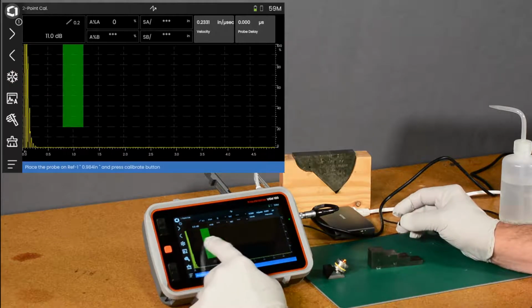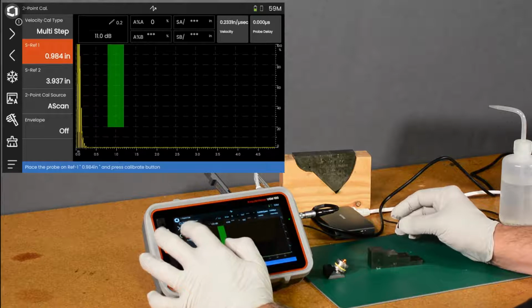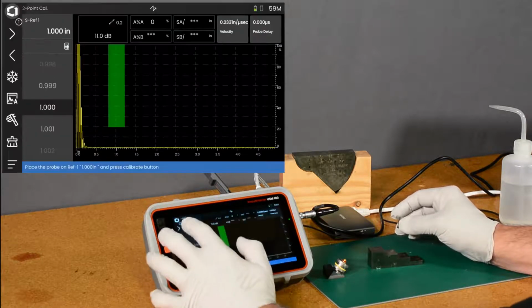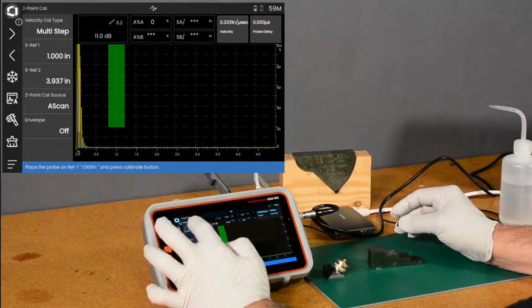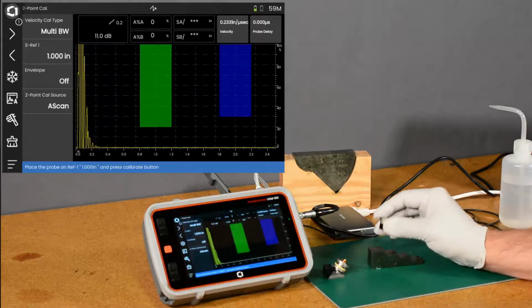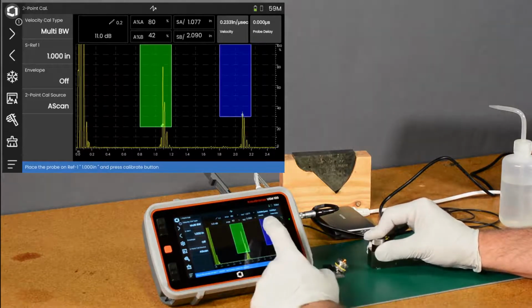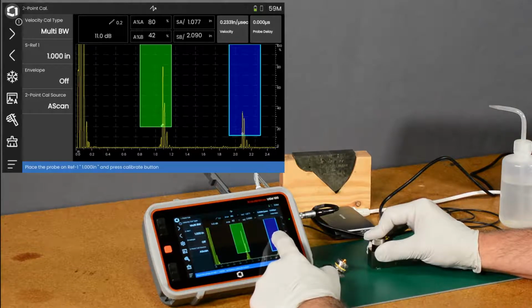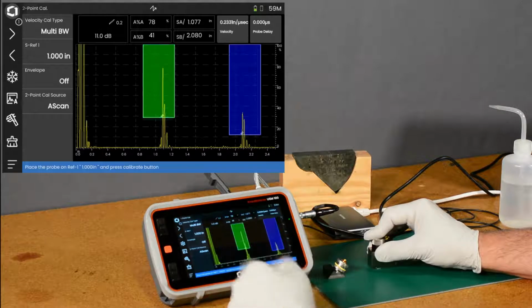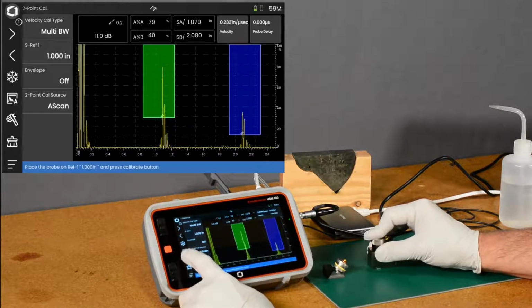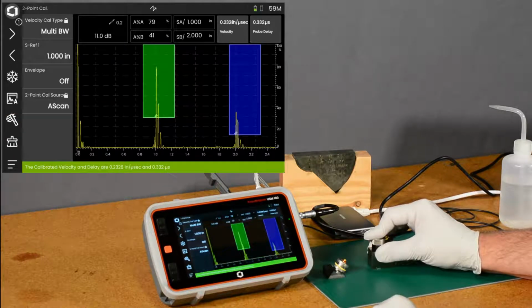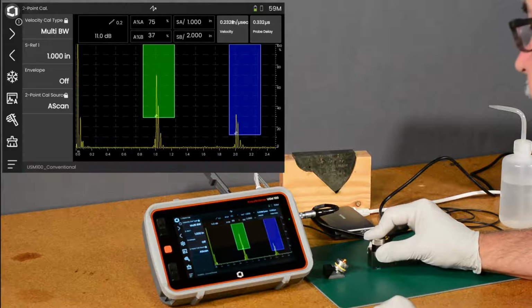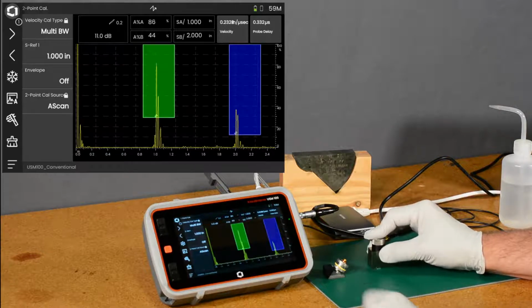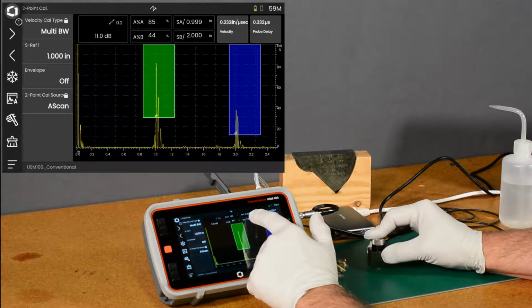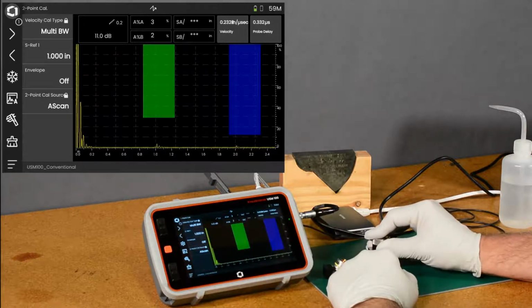And I'll swipe out my sidebar. I'm going to calibrate on the 1 inch thickness, so we'll change that to 1 inch. And I'm going to make use of our multi-backwall calibration. So this allows us to do the calibration in one quick step. I'm going to drag my gate B here so it's about the same place on the flank as gate A. And all I need to do is hit the calibrate button, and our calibration completes. And it looks like we measured 0.2328 inches per microsecond of velocity and 0.332 microseconds of delay. Notice our reading up here for sound path in gate A is rated at 1 inch, 0.999.